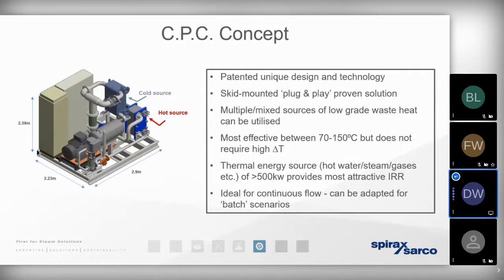And a CPC is basically a skid-mounted solution that allows the high-temperature effluent to cause a phase change of a refrigerant gas, and that expanding gas can then turn a turbine to generate a small amount of electrical energy before that refrigerant gas is then cooled and the effluent, having lowered in temperature, is passed away to waste. So the cost benefit is measured partly in the electricity that's generated, but mainly as the reduction in cooling costs as a result of no longer requiring to pass that high temperature effluent across a cooling tower. But I just want to show a very quick animation that's probably going to show this concept a little bit more clearly.